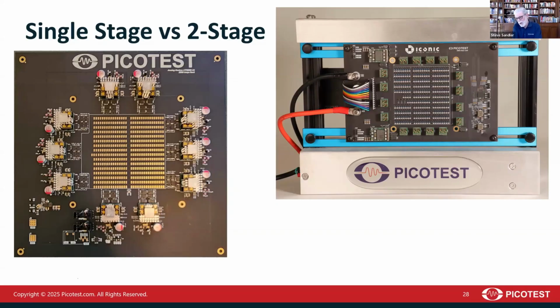If we look at the one on the right, that's much more typical of what we see today. There are two 48 volt to 12 volt bricks, and almost every major company makes those. They're extremely efficient, very high density. Each module can get to more than 1500 watts, typically in the 95 to 98% efficient range depending on power. So getting from 48 — or actually data center is really 54 — to 12 or 54 to 13 and change, is really efficient through those two modules.